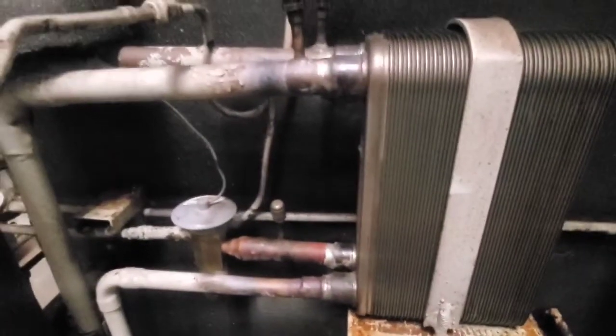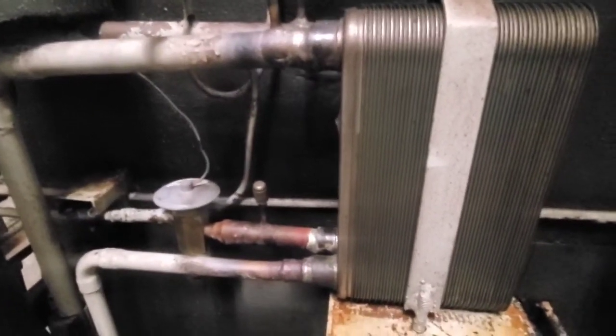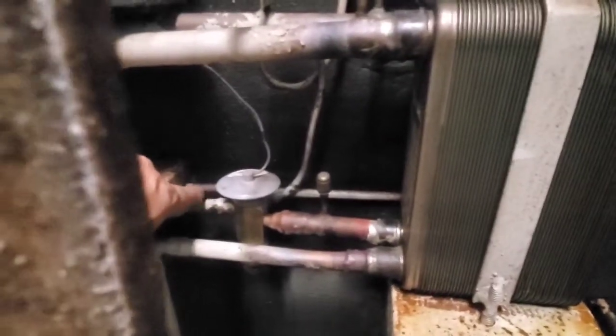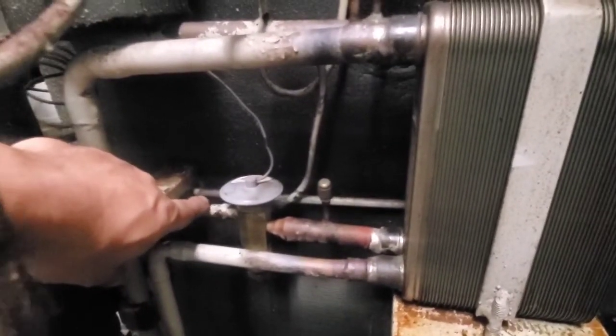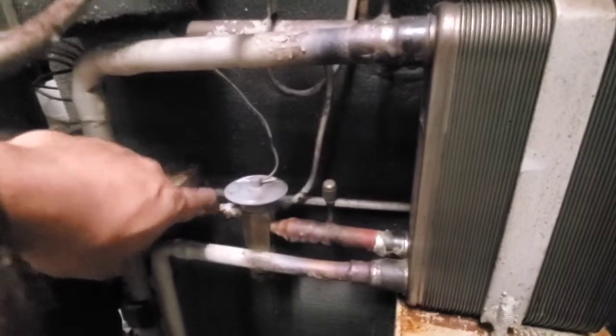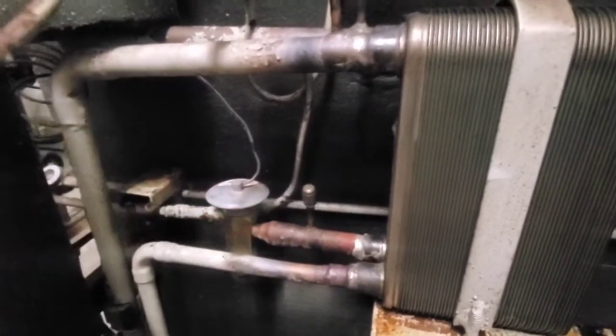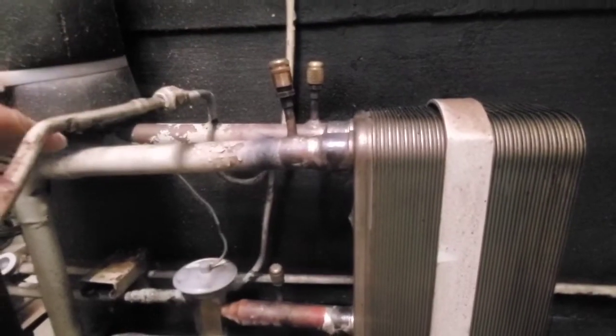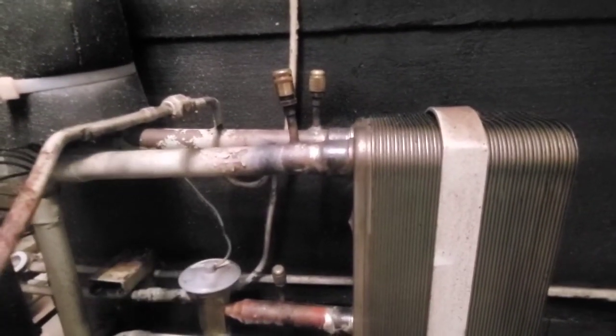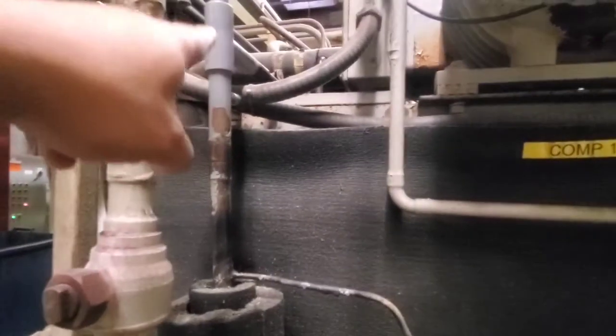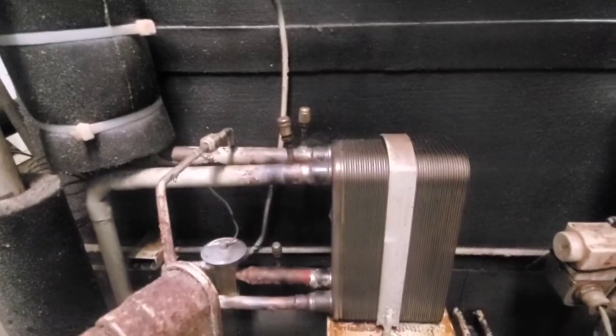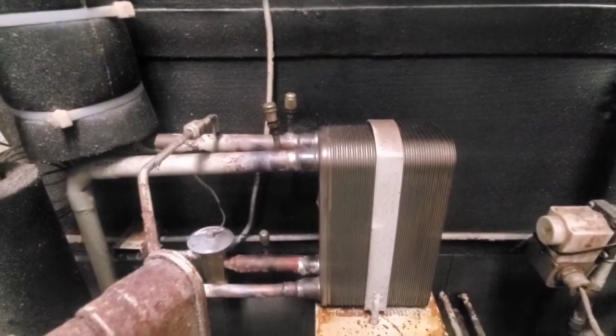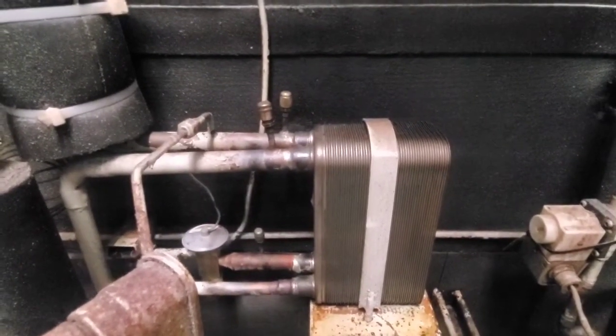And this oil cooler circuit is what we've been working on. This is just a simple refrigeration circuit that pulls a small liquid line from the system liquid line, passes it through a TXV, goes in this brazed plate heat exchanger, cools the oil down. The cool oil goes to the compressor. The return suction gets tied back up to the suction line to return to the compressor. So it's a little mini refrigeration cycle inside this bigger refrigeration cycle that cools the oil down.